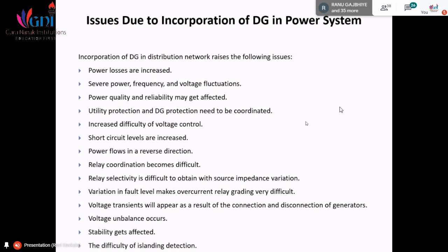The next point is that variation in fault level makes overcurrent relay grading very difficult. We have current graded protection and time graded protection, that kind of protections in our system. So our overcurrent relay will have time graded and current graded settings. Because of the introduction of this DG, the fault current and short circuit current are going to change. In that case, overcurrent relay grading is found to be difficult when the short circuit current level or fault current level changes. So that is another difficulty faced by the utility.